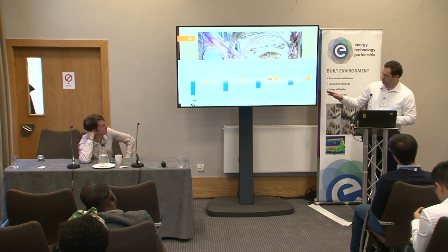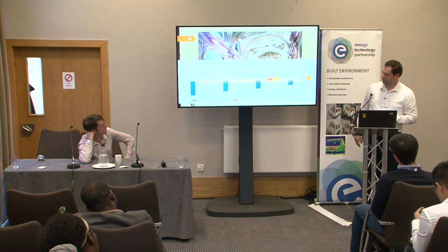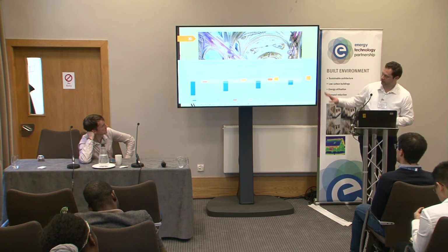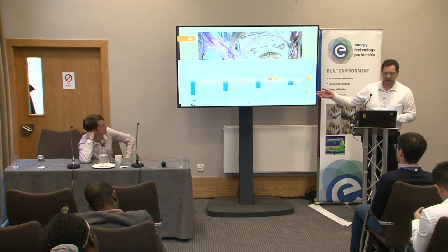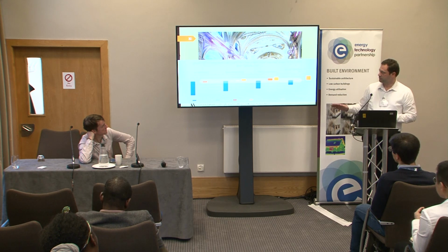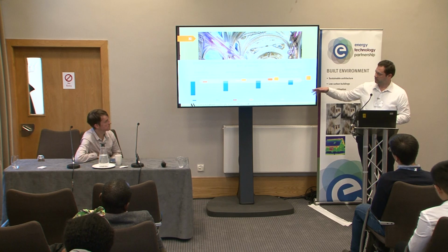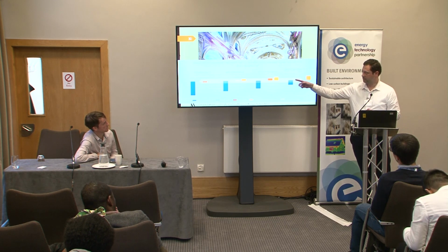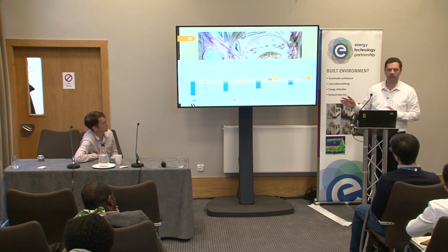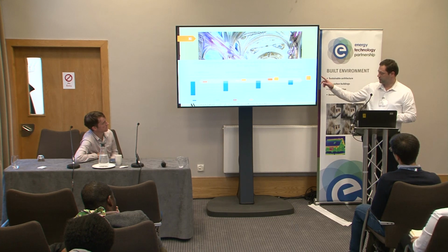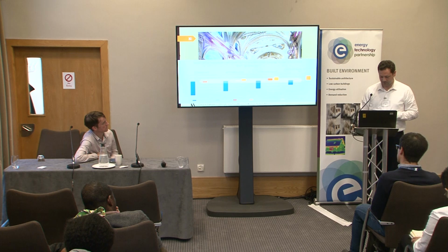So I've modelled, or calculated, different activity levels and what that would mean in terms of comfort. The yellow band is where most people would find comfort. So in a non-heated church on the far left, if you were just sitting in it, it's dreadfully uncomfortable. But if you're doing some different activities, at 3 METs, which is light dancing, you would maybe find that was fine. As you use the radiant system to add radiant energy into the building, you're still okay with the comfort level. Certain output levels might push people into being overheated, and then the gas boiler scenario running four times a day has a mix of comfort levels.